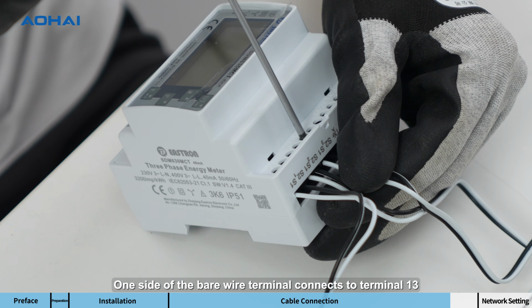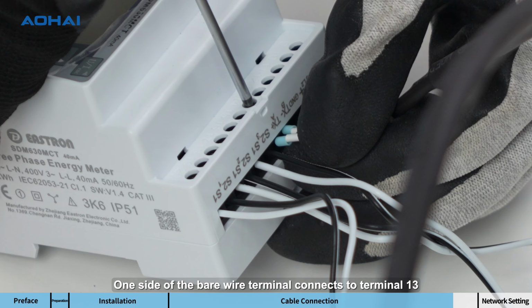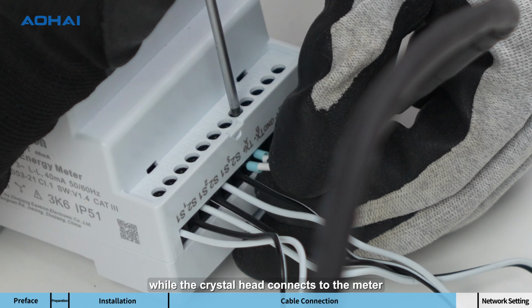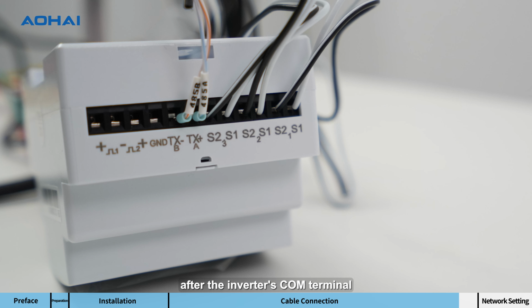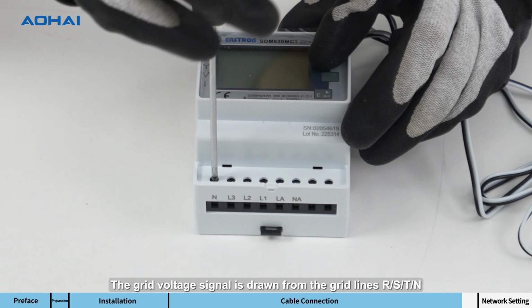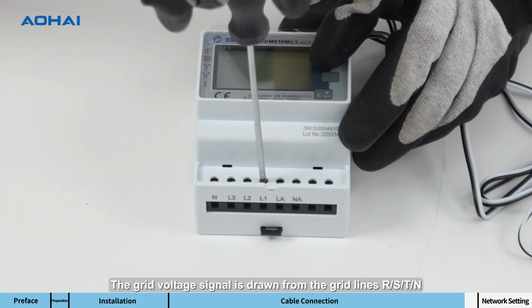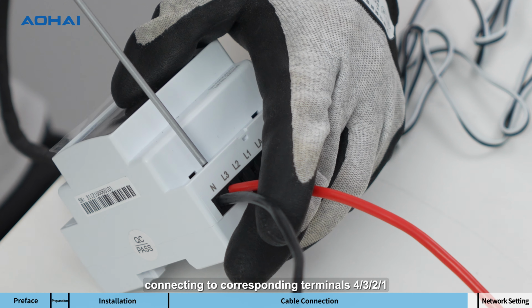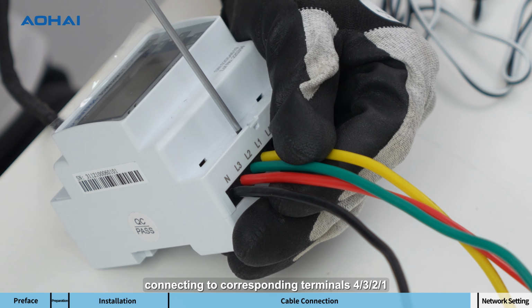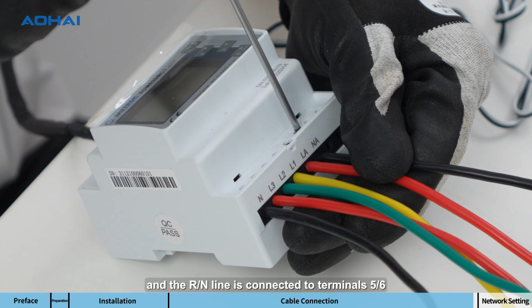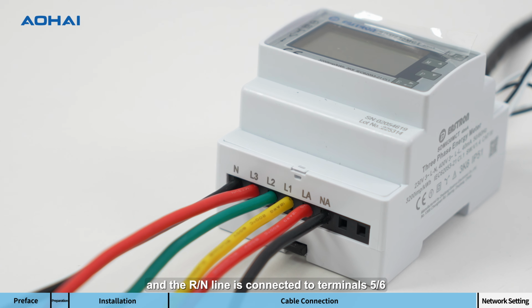One side of the bare wire terminal connects to terminal 13, while the crystal head connects to the meter after the inverter's COM terminal. The grid voltage signal is drawn from the grid lines R, S, T, N, connecting to corresponding terminals 4, 3, 2, and 1, and the RN line is connected to terminals 5, 6.